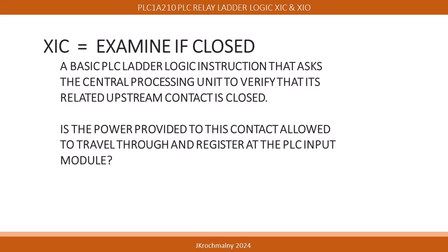Probably the easiest set of PLC relay ladder logic to understand is the Xic, or examine if closed instruction. Xic, or examine if closed, is a basic PLC instruction that asks the central processing unit to verify that its related upstream contact is closed. Or, is the power provided to this contact allowed to travel through and register at the PLC input module?